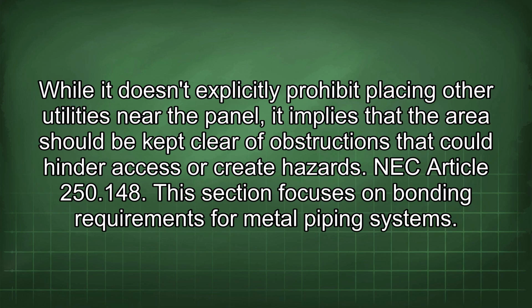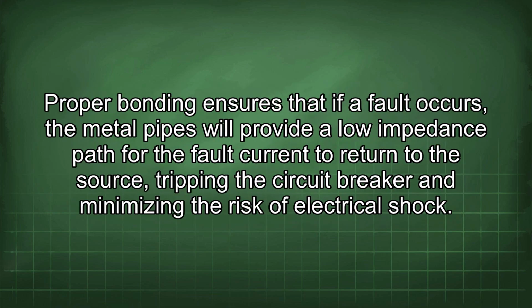NEC Article 250.148. This section focuses on bonding requirements for metal piping systems. Proper bonding ensures that if a fault occurs, the metal pipes will provide a low impedance path for the fault current to return to the source, tripping the circuit breaker and minimizing the risk of electrical shock.